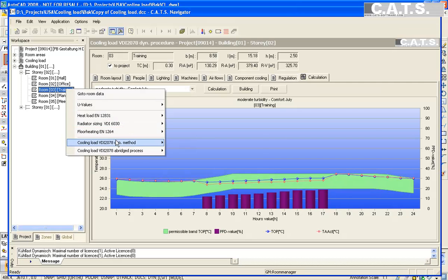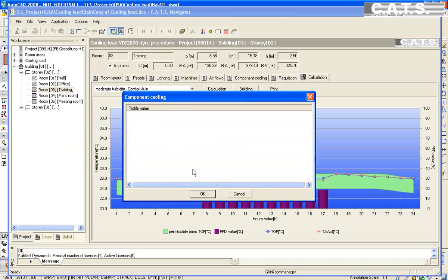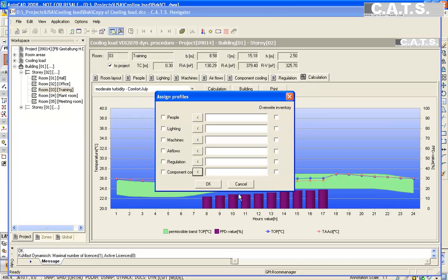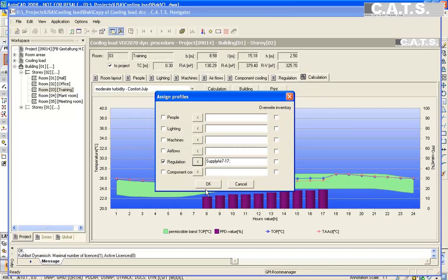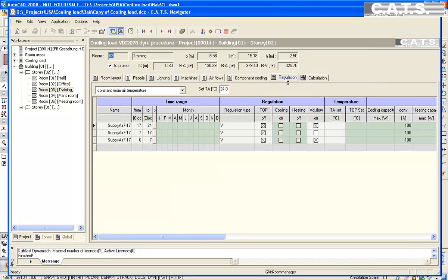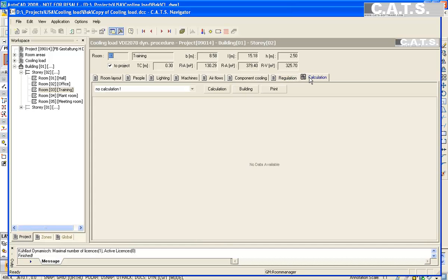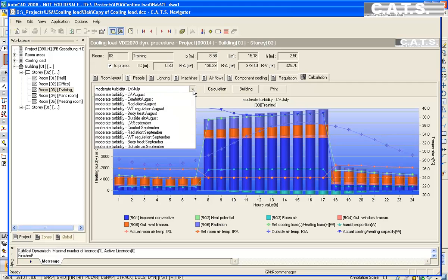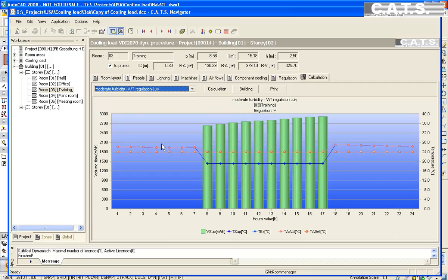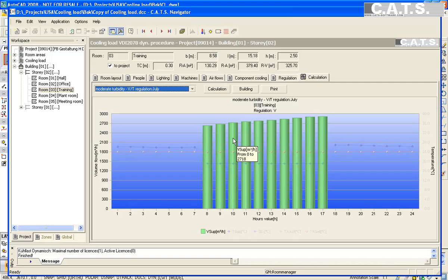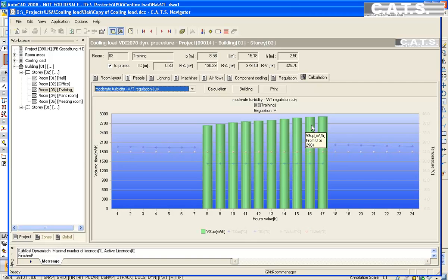By clicking the room tab, we will select a new profile for the room and recalculate the air supply. Select regulation and the tab to the right. When the window appears, select supply air. Select OK. We now see the new profiles. Select calculation. The green columns indicate the required supply to meet the setpoint. The blue line indicates the supply air temperature and the pink indicates the actual room air temperature and the orange line indicates setpoint.